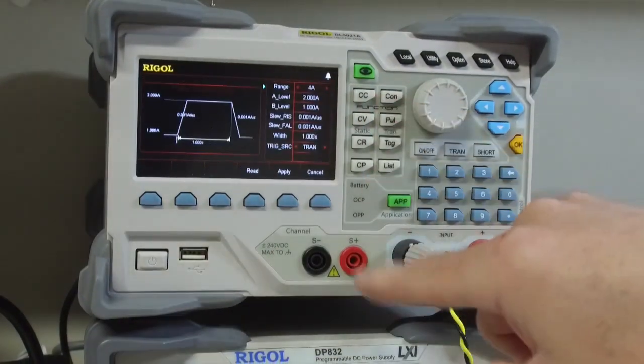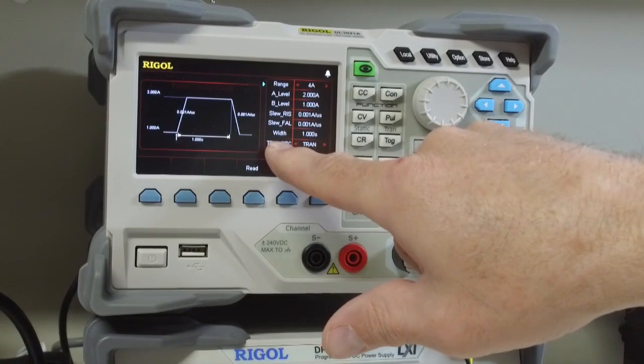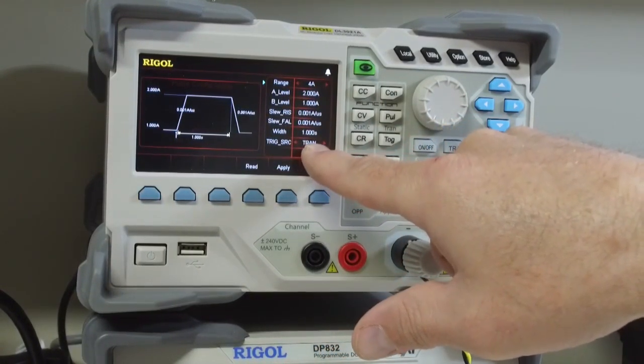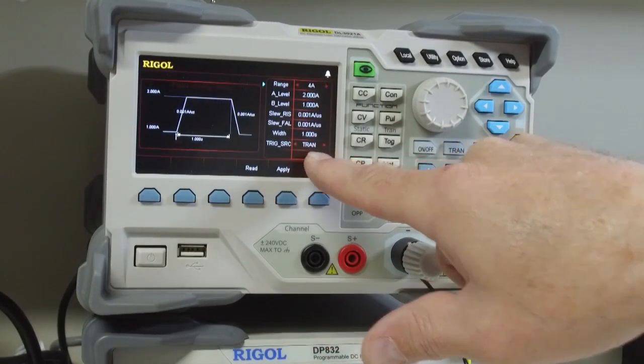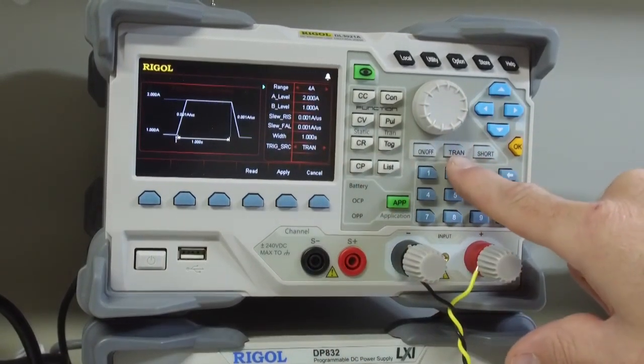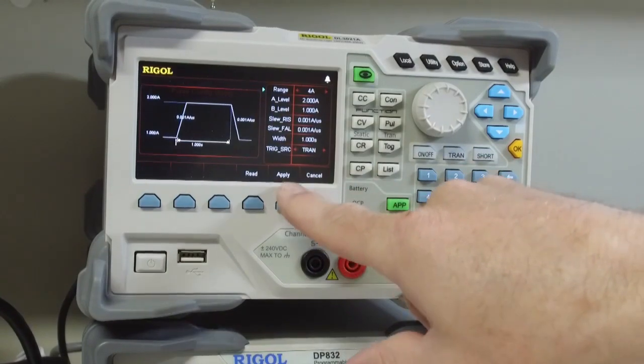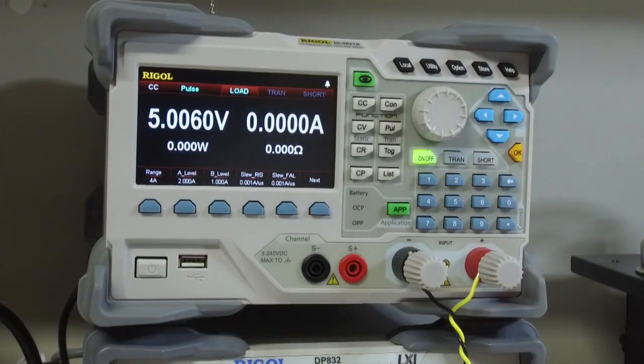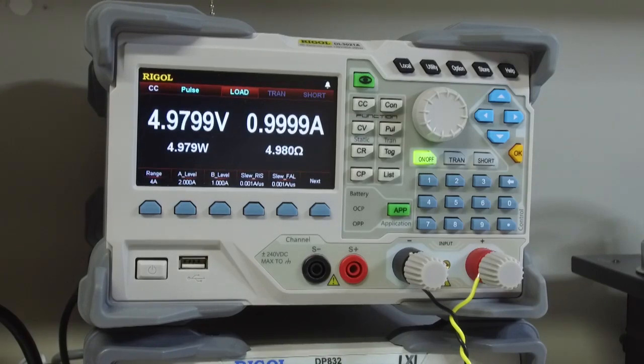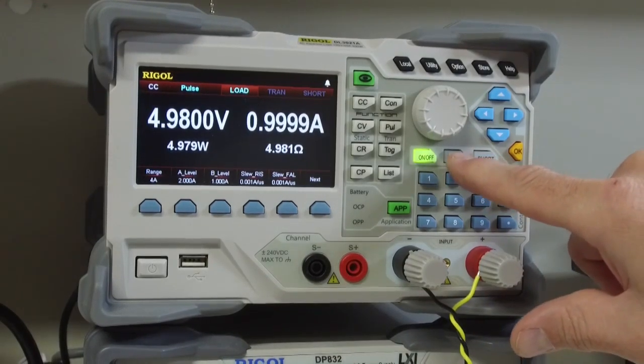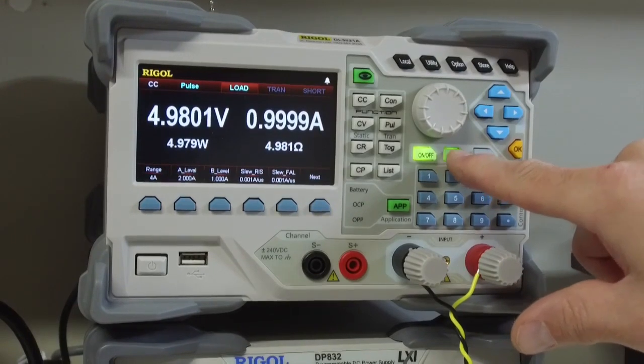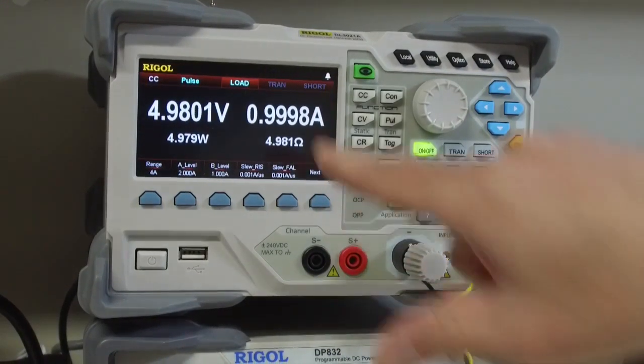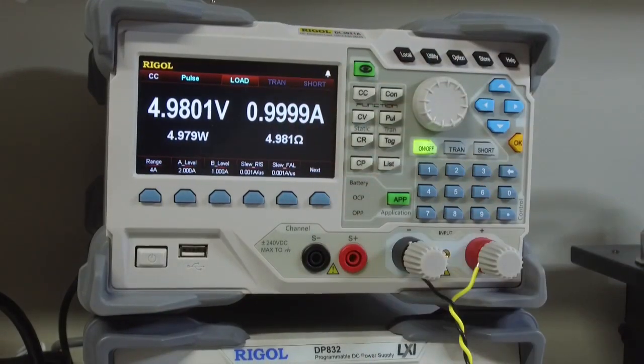Let me show one more thing. This is the trigger source. And there's a couple of different options. Transient is associated with this button here. So I'll hit apply. And what this will do is I'll turn on my load. And when I hit transient, it will apply that one second pulse. And we saw this go up and then come back down for one second.